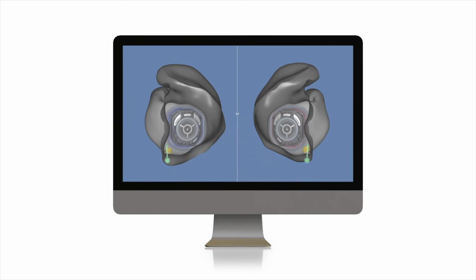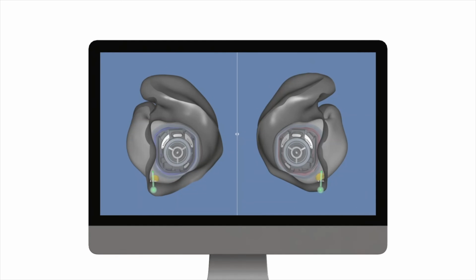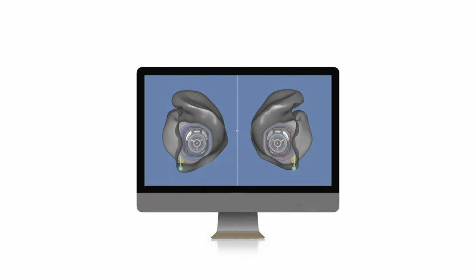Acoustically optimized receiver selection includes a calculation of several different variables to determine the most appropriate receiver or speaker size inside of the hearing aid instead of just relying on hearing loss threshold data from your hearing care professional. They actually have an algorithm that they use to determine the most appropriate size of receiver based on several different variables about your hearing and your ears, both for low frequency hearing and high frequency hearing, as well as the potential progression of your hearing loss over time. This way you don't have to worry about getting hearing aids today and having those hearing aids still being appropriate for you 5 years down the road if your hearing has become worse.